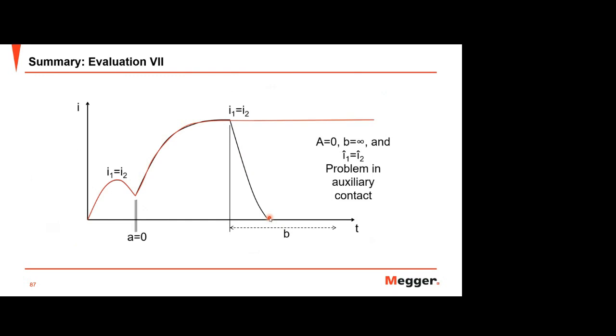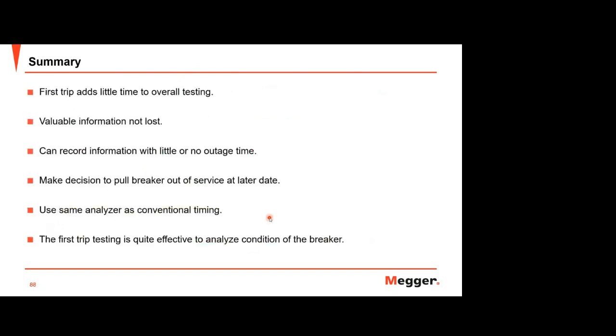Where is the function of this aux contact? To remove the current, to cut off the voltage here. So this is the summary. I can say this first trip adds little time to overall testing, but still gives valuable information. At least you don't lose any information, rather than doing no testing. A first trip test is still better than not doing anything. You can record information with little or no outage time.